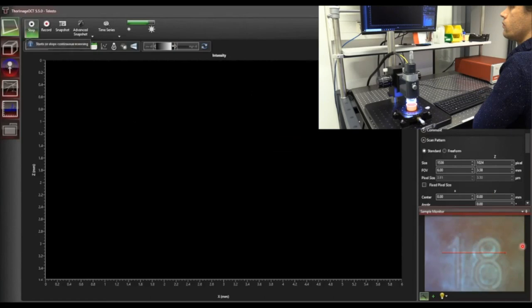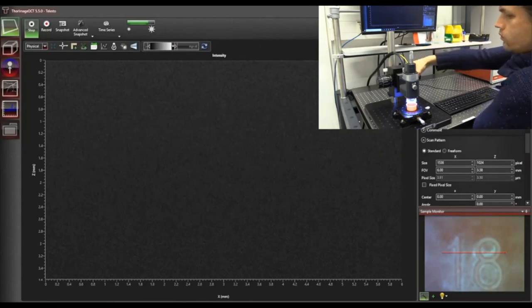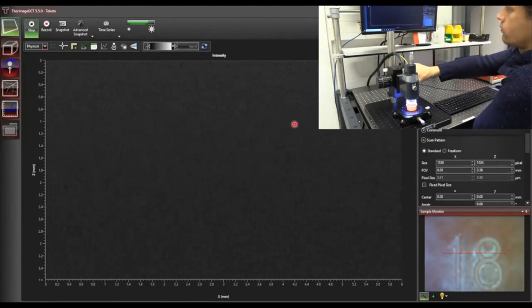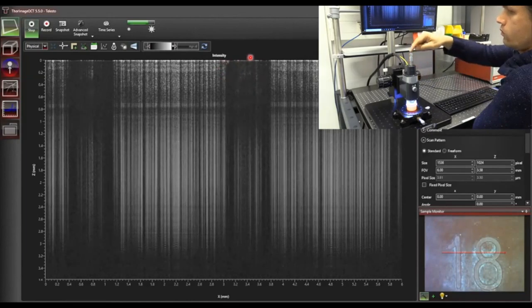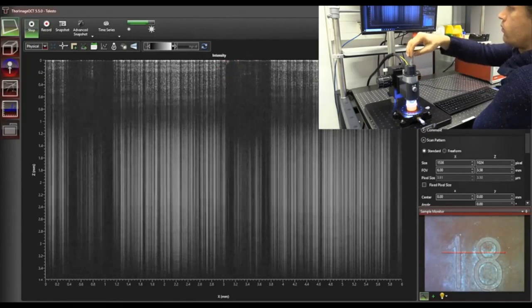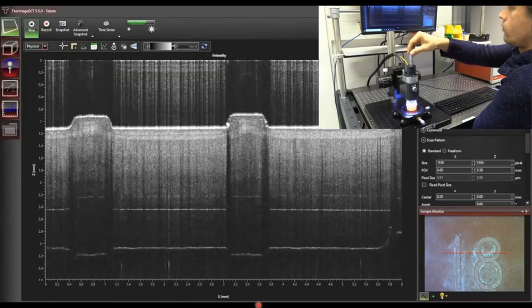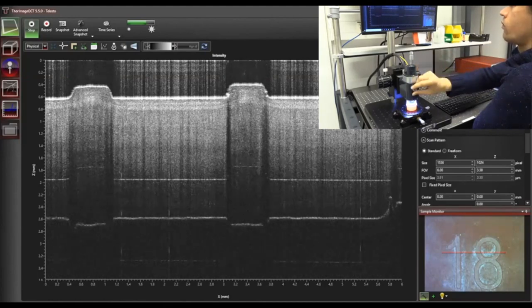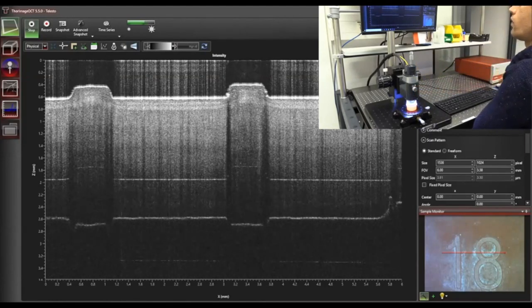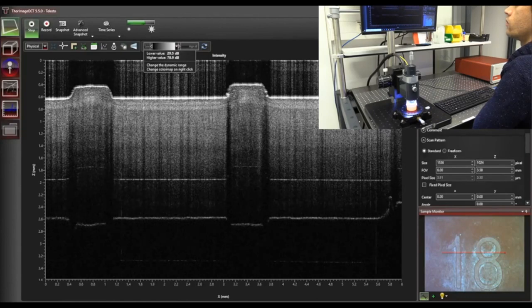Here is a video of the red cap sample — it's out of focus and the OCT image is blurry. I change the dynamic range so you can see the noise. I then adjust the focus, and once in focus you see autocorrelation appearing at the top — an artifact Steve will discuss later. I then change the reference arm length and the image moves in and stays in focus. After some fine adjustments, we have our OCT image. I then change the dynamic range again for a clean result.